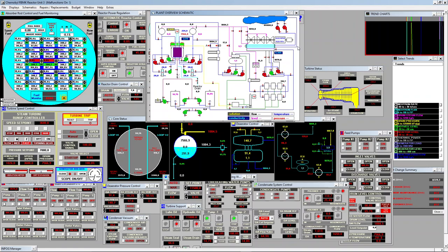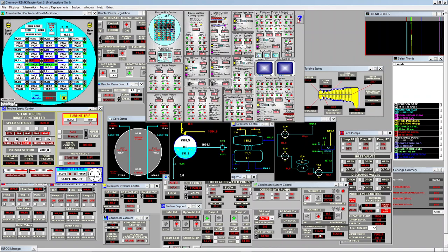So this is basically dirty water with minerals and organic matter, and if there is some leak in the condenser, this water will pollute our demineralized water. So conductivity will start going high and the polishers will start to clog up. So if you see this conductivity going up very quickly while the polishers are still okay, for sure at some point of the system you have some pollution, probably in the condenser. For the moment it's totally fine, below 2%, totally okay.